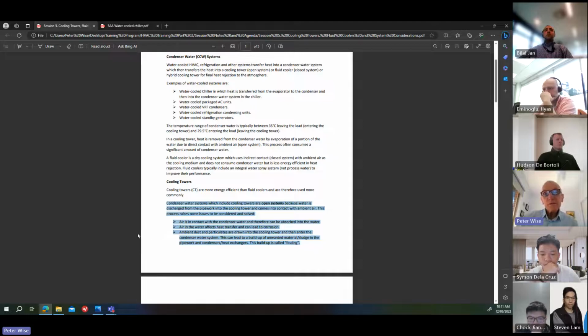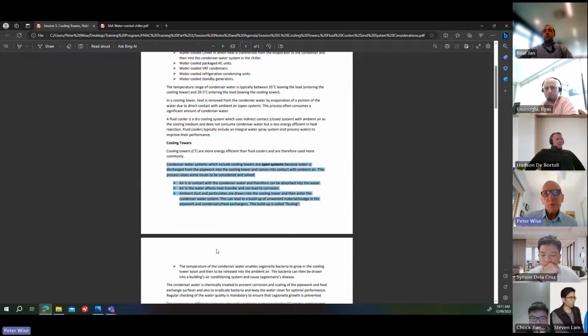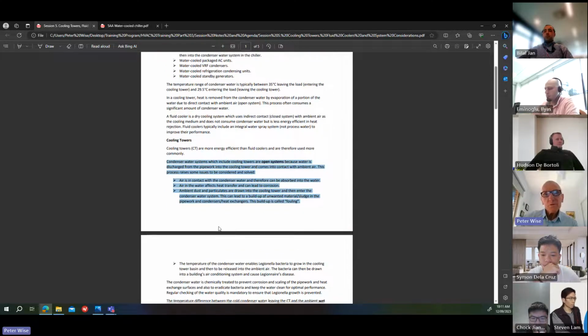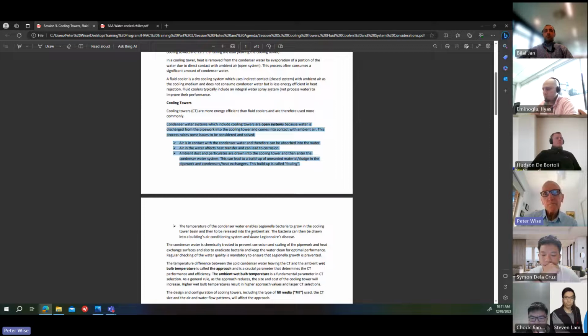Ambient dust and particulates are drawn into the cooling tower and then enter the condenser water system. So any dust in the air is taken into the water and can get into your system. This can lead to a buildup of unwanted material or sludge in the pipework and the condensers or heat exchangers. The buildup of this material is normally called fouling. So you've probably heard the term fouling in heat exchangers. So I need to be aware of that.